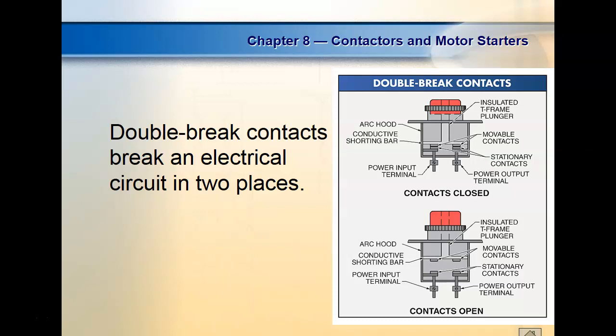A lot of your switches, a lot of your push buttons, a lot of your relays are used for this. When passing double break contacts around, notice that the contacts of the switches are actually sprung, double break. And notice they kind of close. They have a little spring. What happens is contact break creates temperature that allows it to break.